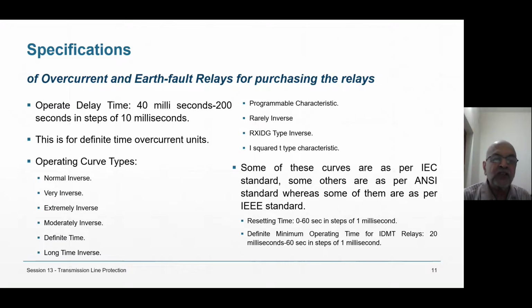Normal inverse, very inverse, extremely inverse, moderately inverse, definite time, long time inverse, programmable characteristics, rarely inverse, RXIDG curve, and I squared T equal to constant. That curve. So many curves. A single relay is giving them. You have to select, no doubt, one at a time.